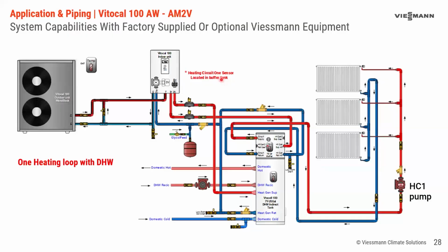So this looks at a different kind of a heating application. So rather than the air handler we looked at, this is a series of panel rads. And in most cases, these panel rads are going to be heating only. I mean, there are panel rads and heat emitter rads or cooling emitter rads. They're designed for chilled water. And if that's the case, you could do heating or cooling. But I think in North America, I'm not really aware of too many applications where we're doing anything but heat with panel rads like these. And I'm showing you in this drawing thermostatic valves on the rads. And that's fine. That works. And that's a very common way to do it.